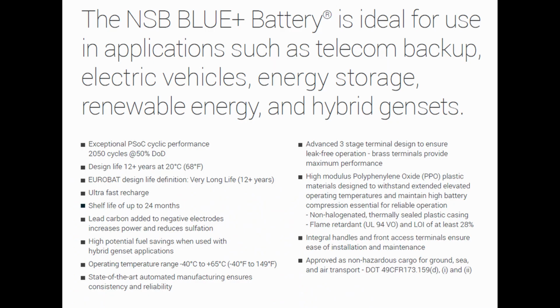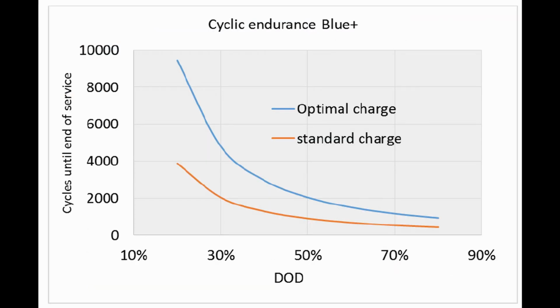Next, let's look at the North Star battery. This one uses a slightly different standard, it's a European standard, but it also has a partial state of charge life of 12 plus years. Now let's look at cycle life of this battery. Here we see that about 4,500 cycles can be achieved, which is enough for 12 years at one cycle per day. This battery will last 12 years if maintained properly. Now for the lithium battery.